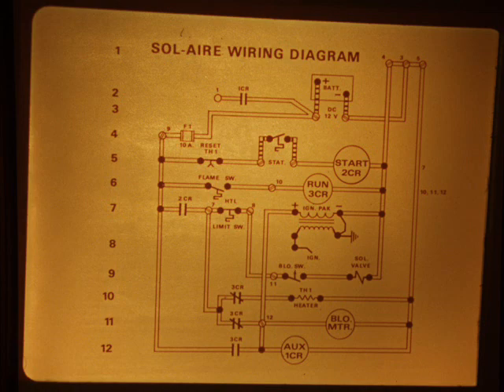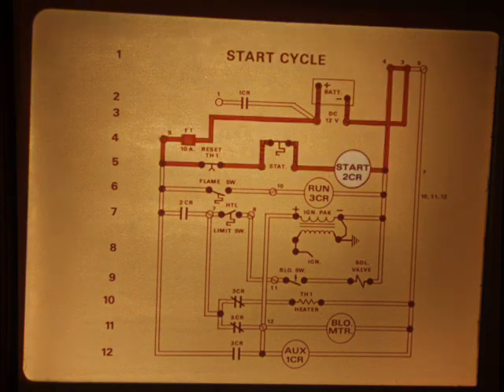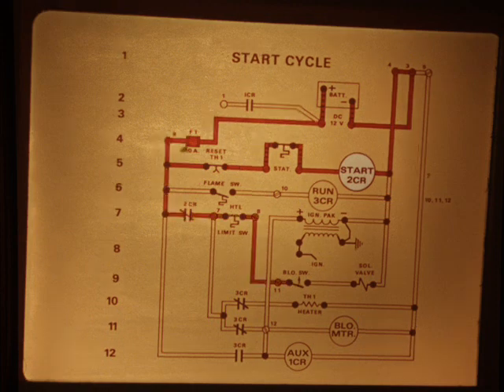Now, let's see how the furnace works by explaining its three operating cycles: the start cycle, run cycle, and purge cycle. This is the wiring diagram for the furnace. Terminal and wire numbers are marked to correspond to the numbers on the control box and the flags on the wires. The start cycle begins when the thermostat closes, calling for heat from the furnace. Power is supplied through the fuse, the thermal reset relay, and the thermostat switch to energize the start relay and close its contacts. With the start relay closed, power goes through the high limit switch to the blower centrifugal switch, which you'll remember controls the gas valve.